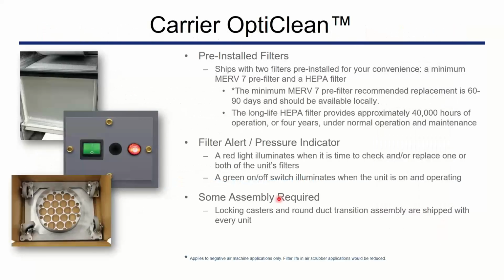So there's a pre-filter on there, and there's dirty filter indicator lights. So the occupants, i.e. the teacher in your case, knows the filter is dirty, and they can put in a maintenance request for you guys to change the filter. As opposed to changing them randomly, hopefully you're changing them when they're actually dirty. You can still do them on a schedule if you want, change every X amount of months, or you can wait for the indicator light.